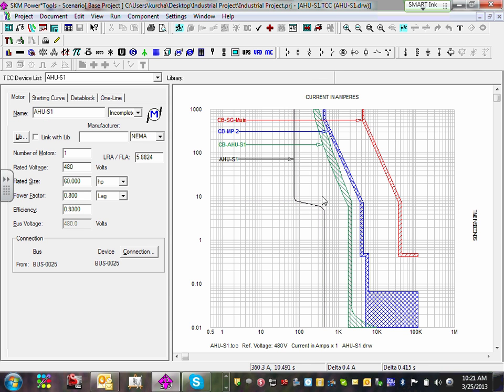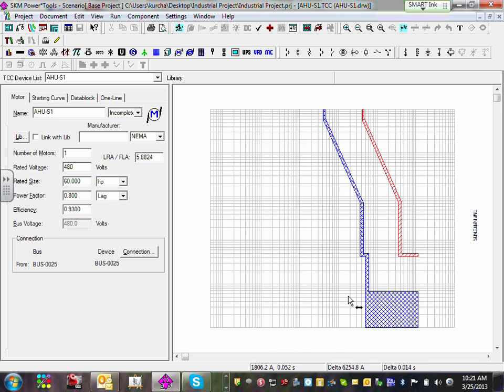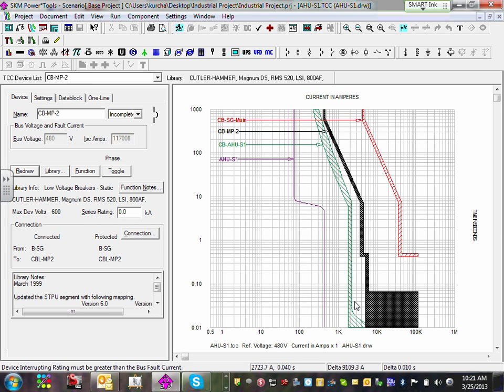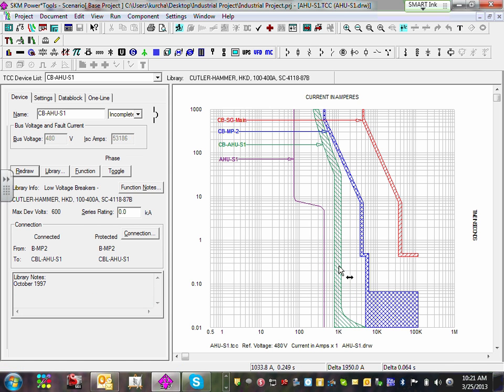Now your goal, gentlemen — can you see that they're coordinating here? We're coordinating a little bit, but miscoordinating at that edge. So grab that leg, can you see it, and move it slowly to the right. The goal of the coordination curve is to make sure that start curve doesn't overlap with the overcurrent protection device. The goal of the coordination is to make sure the overcurrent protection device that protects the air handling unit still allows it to start. As you can see, it's allowing it to start — it's not overlapping here. And at the same time, it's coordinating with the main of the panel as well as the main of the switchgear.